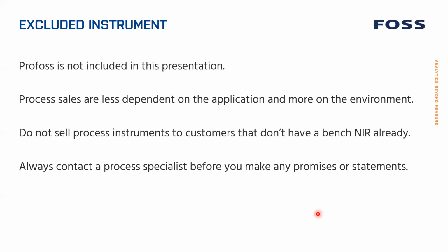Okay, before I now start going through all the different instruments, I have excluded ProFoss because ProFoss is a process instrument and it's not so dependent on the application as it is on where you're actually going to place it. And in principle, we always need to do some application development for a process instrument. And my general recommendation is don't sell process instruments to customers if they don't really already have a bench instrument. They need to be aware of the pros and cons with an NIR before they start to put it into a process environment. It is much more complicated to do that than have a bench instrument.